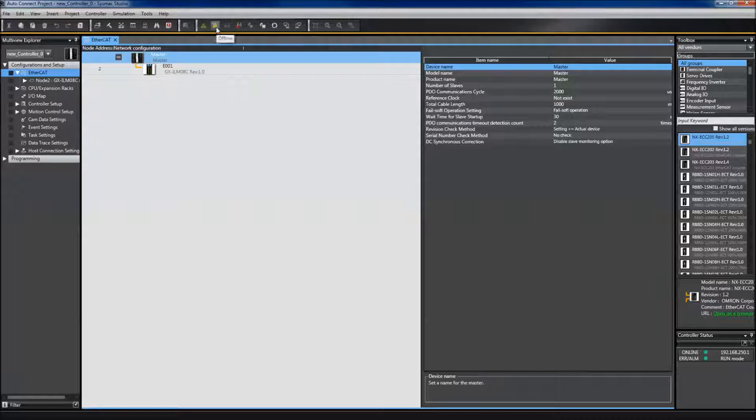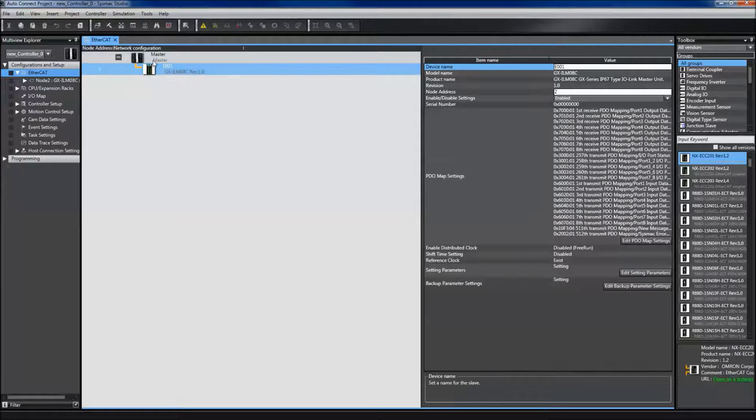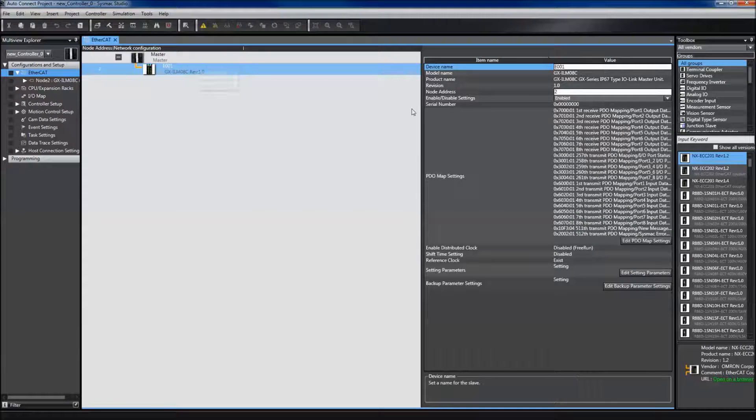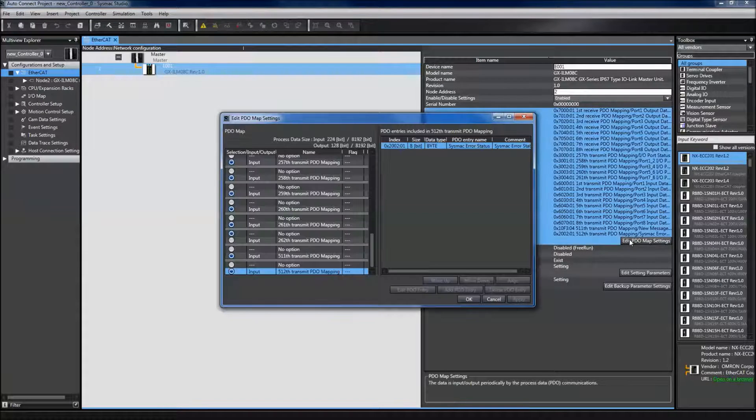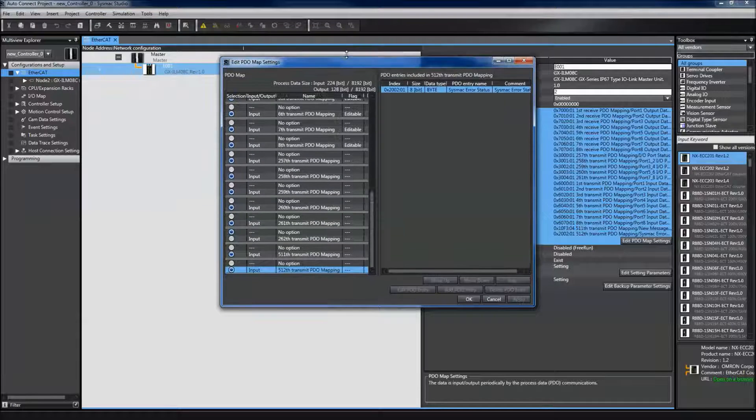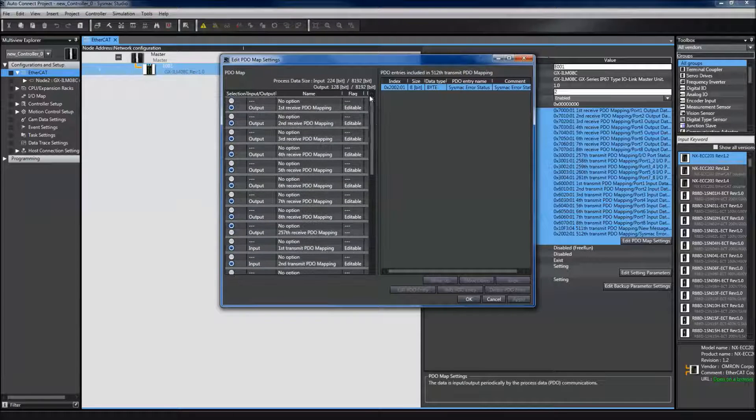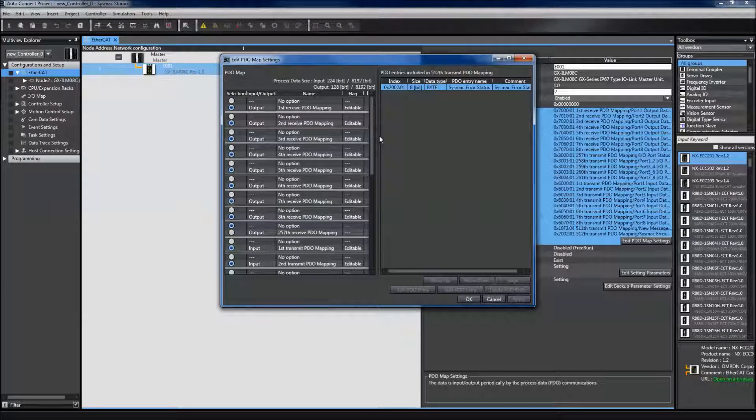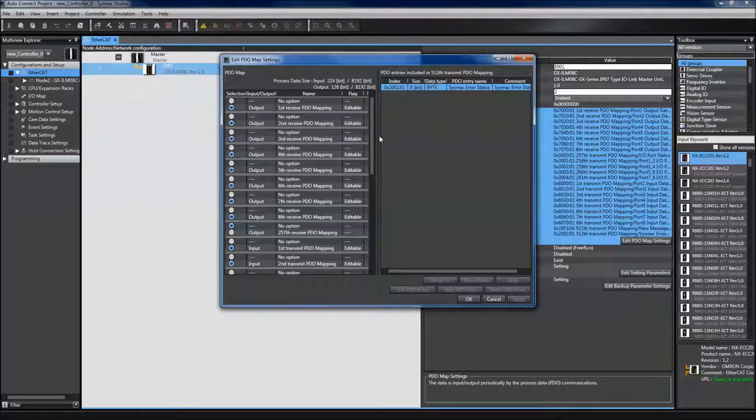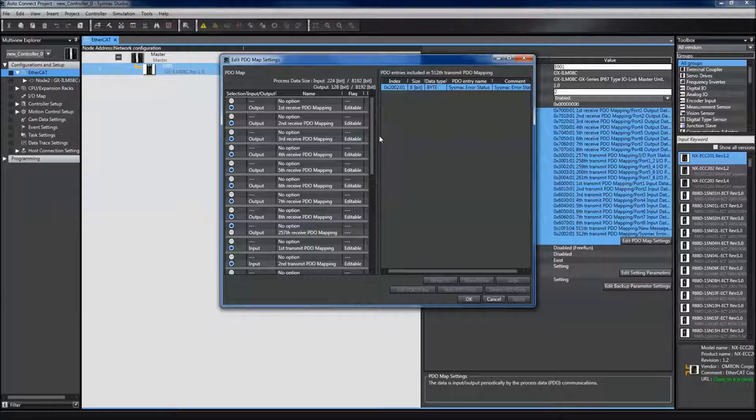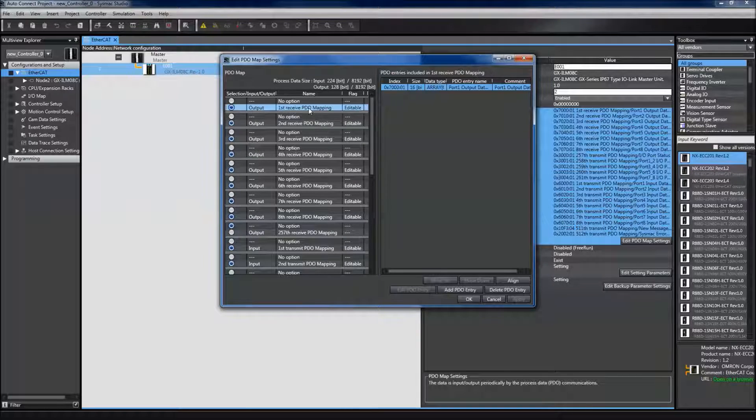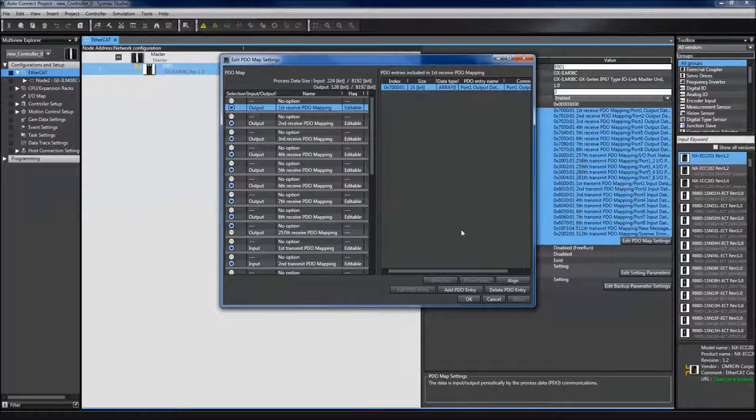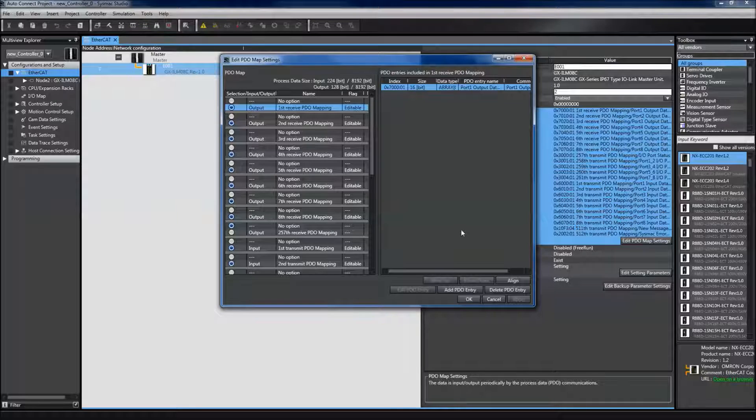Now I'm going to go offline and double-check all of my EtherCAT parameters. The first thing I need to check is the PDO map. I need to edit the PDO map settings if any of my IO-Link devices are sending or receiving more than two bytes. In this instance, the Omron photo sensor only sends two bytes to the IO-Link master, so this will stay as the default. I have another video that will address how to do PDO mapping with more than two bytes.